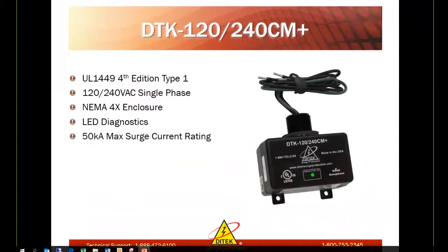The DTK-120/240CM+ is a UL 1449 4th edition Type 1 device as well for 120/240 single phase. It's in a NEMA 4X enclosure with LED diagnostics. This does also have 50 kA of surge current per phase, 25 kA per mode. This is a perfect device for HVAC equipment fed from a disconnect, like an HVAC condenser. We do highly recommend that for external HVAC equipment, as well as pool pumps or well pumps.